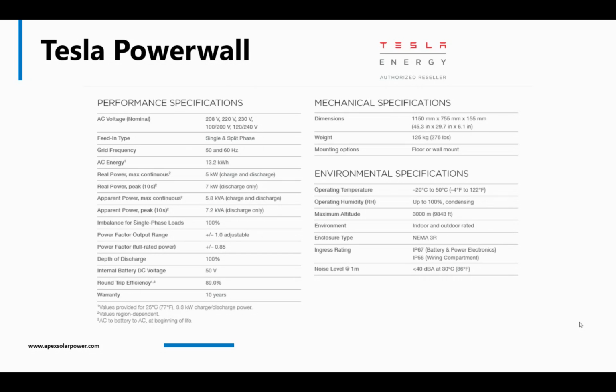Anything that's on a double pole breaker or a double breaker may lend itself to requiring 2 Powerwalls. 2 Powerwalls combined gives you 50 amps. So any really heavy load requirements, whether it be geothermal, welding equipment - I know that sounds silly, but we have customers with welding equipment, hot tubs, some people find that's a priority, I don't know if I would - electric vehicle charging. Those are all heavier loads that require upwards of 50 amps, and we're going to recommend that you get 2 Powerwalls. If you don't have any of those heavy load requirements, 1 Powerwall is all you need, certainly for priority loads, and it may take care of your entire home.